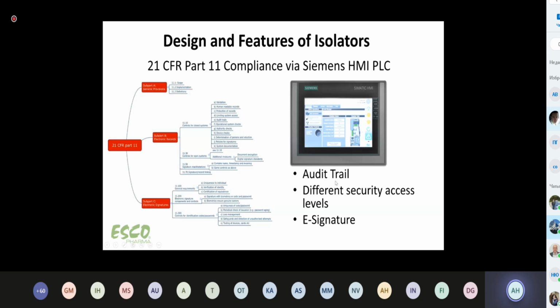An audit trail is a step-by-step workflow of a particular process of the isolator at any given time or day. It is all captured step by step. You also have to put in security access depending on the qualification of the user, whether he's a normal operator, a supervisor, an administrator, the engineer, or the factory. And every report that you print out, for example the pressure hold test report, the biodecon report, or the alarms report, should of course be signed off by the person with authority. So the report must also incorporate a non-changeable electronic signature.